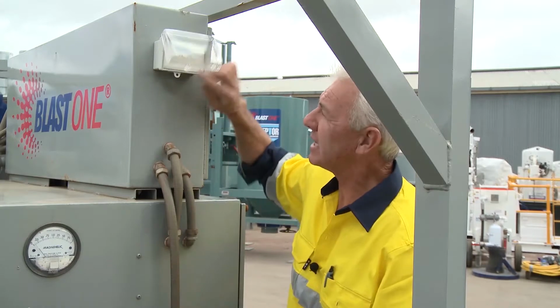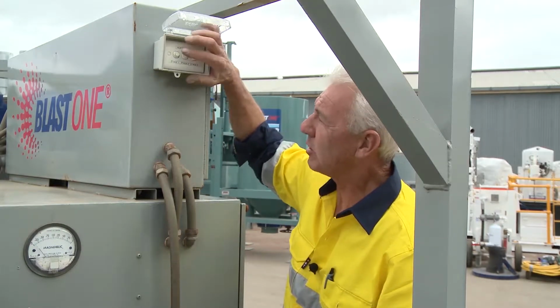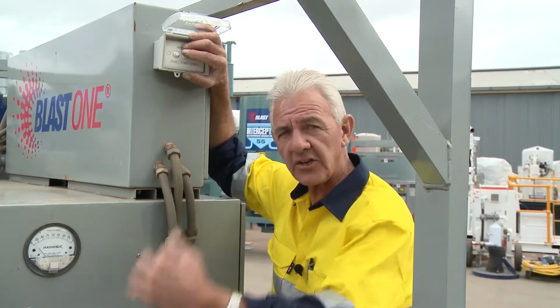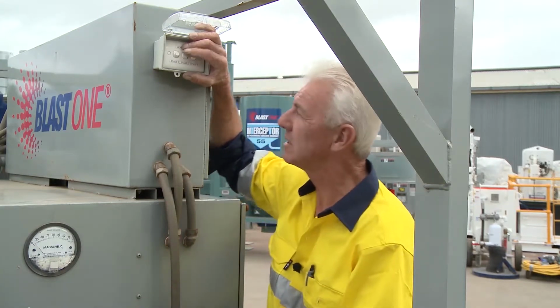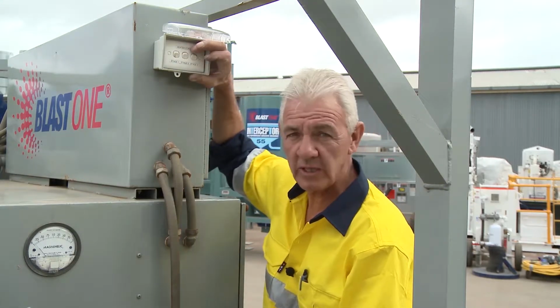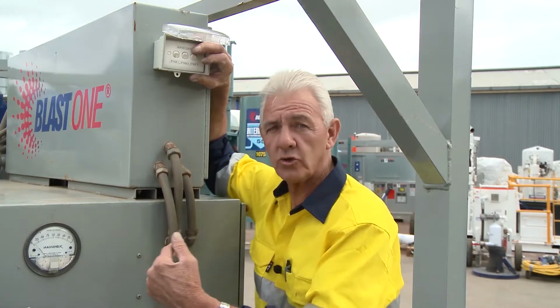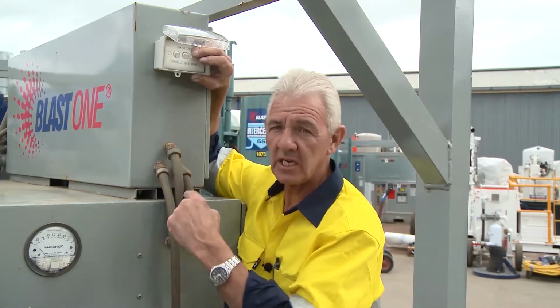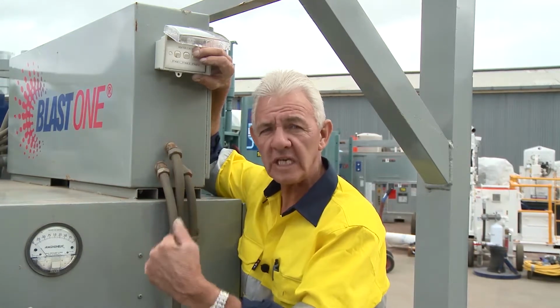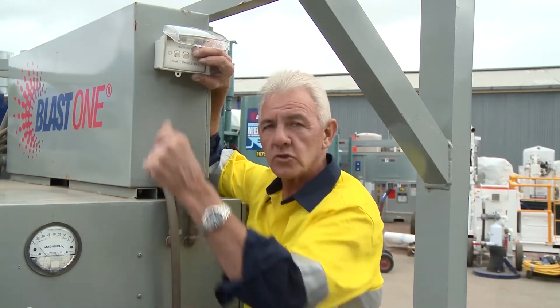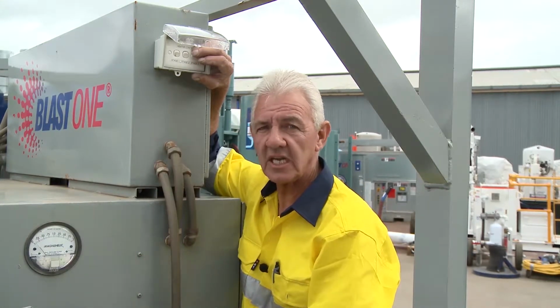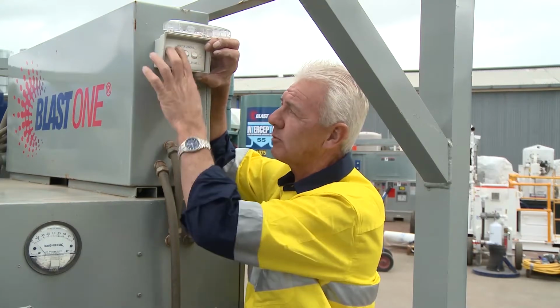They're set up like that primarily because it needs time to facilitate each heater bank as it comes on. If you bang them all together at once, the load on your genset becomes overwhelming and the genset shuts down. So it gives everything time to appropriate itself.